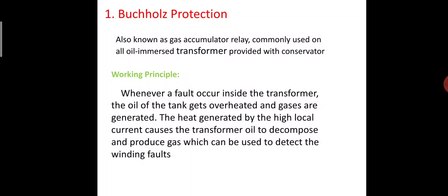Next one, Buchholz protection. Also known as gas accumulator relay, it is commonly used on all oil immersed transformers provided with a conservator. It is used for protection of oil filled transformers from incipient faults below oil level.